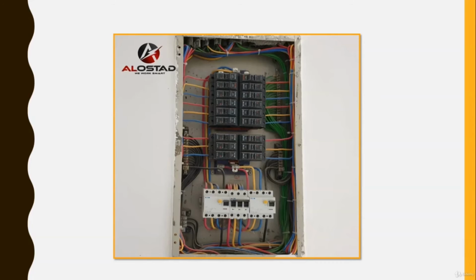Look here at the outgoing MCBs. It's clear that they are divided into three different colors, which refer to the three-phase wires: red, yellow, and blue. Since the incomer breaker is three-phase, the three-phase voltages must be divided among the MCBs. As you can see, we start with red phase, yellow phase, blue phase. Again, red, yellow, blue, and so on. Never mind, you will understand it more later.